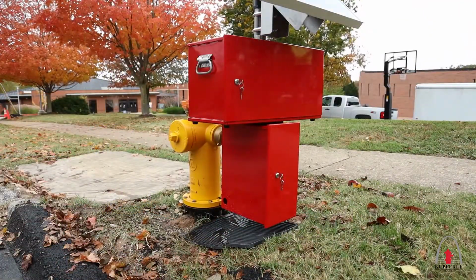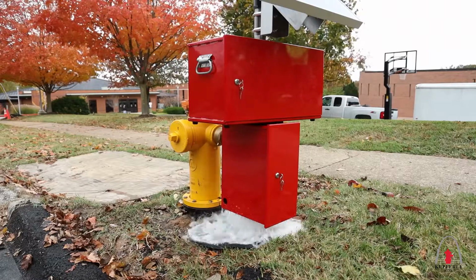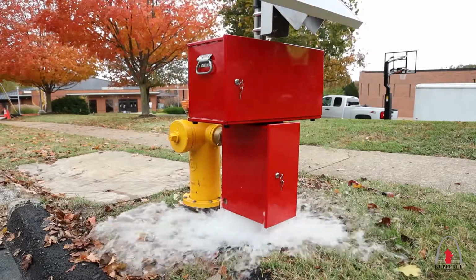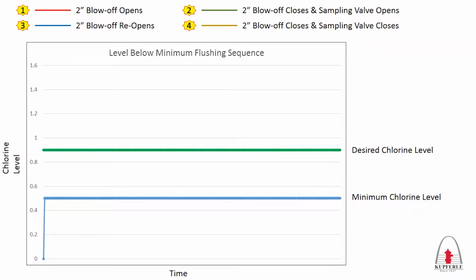Once this is done, unit will automatically maintain residual program parameter levels in the following order of events. At the program sampling time, the unit will begin with an initial blow-off to remove old water and obtain a sample from the main, usually 1 to 3 minutes.